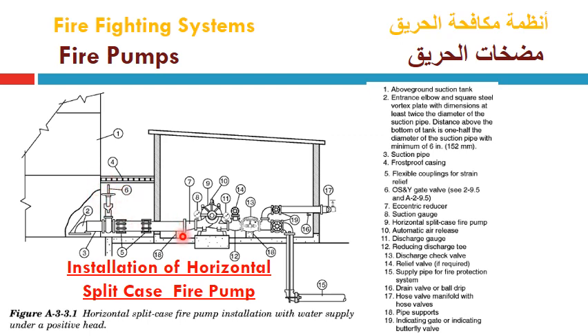And then number 7, the eccentric reducer, which we have discussed before, and its right configuration of use. Then number 8, the suction gauge, a pressure gauge on the suction line. The horizontal fire pump is number 9. Number 10, the automatic air release valve, which is affixed to the pump casing to prevent air pockets or air voids inside the pump casing. Then number 11, the discharge pressure gauge affixed to the discharge flange.